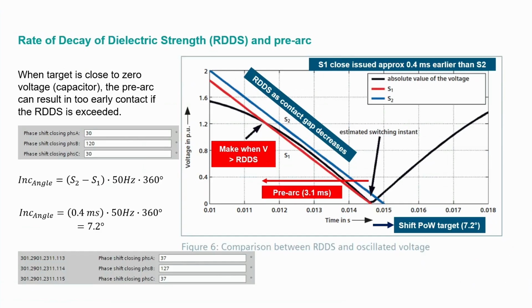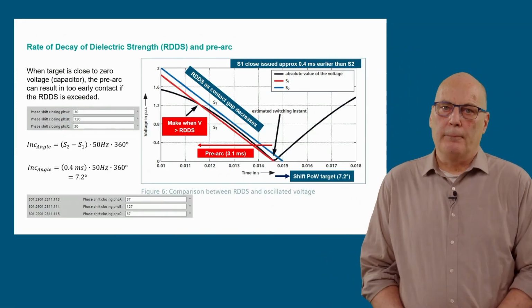A final aspect before we go to chapter 3 is the rate of decay of dielectric strength, simply called RDDS. As will be shown here and again in chapter 3, this can be of importance for some applications, especially for capacitor load closing. What is RDDS? It is a value we can use to determine the pre-arc time. In the diagram, the red and blue curves, S1 and S2, are RDDS curves for two switching times, two instances of closing.